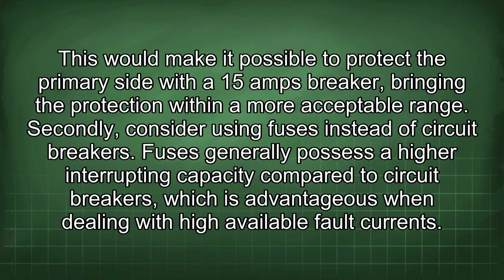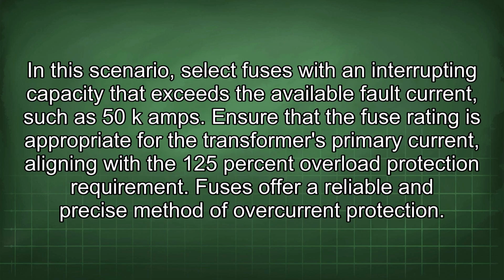Secondly, consider using fuses instead of circuit breakers. Fuses generally possess a higher interrupting capacity compared to circuit breakers, which is advantageous when dealing with high available fault currents. In this scenario, select fuses with an interrupting capacity that exceeds the available fault current, such as 50 kA. Ensure that the fuse rating is appropriate for the transformer's primary current, aligning with the 125% overload protection requirement. Fuses offer a reliable and precise method of overcurrent protection.